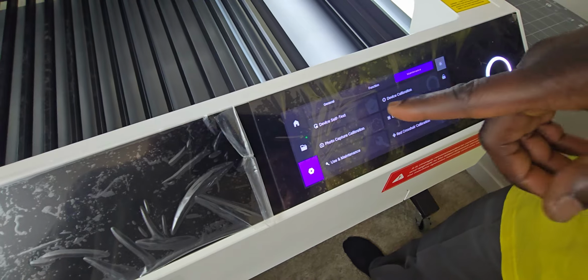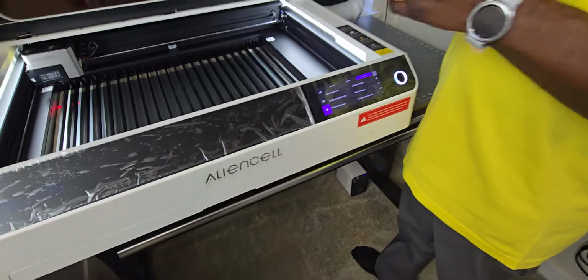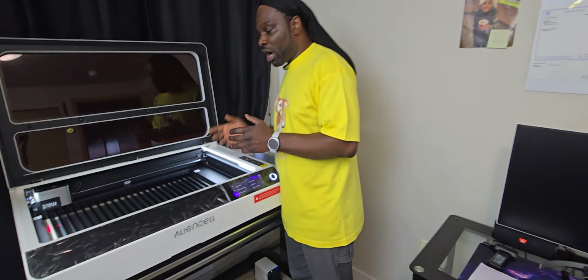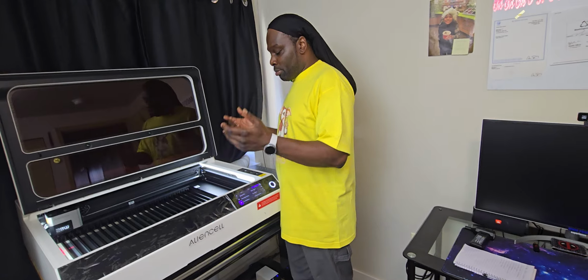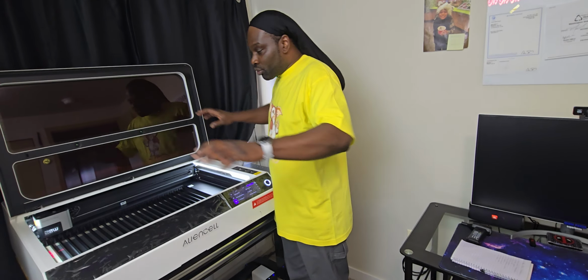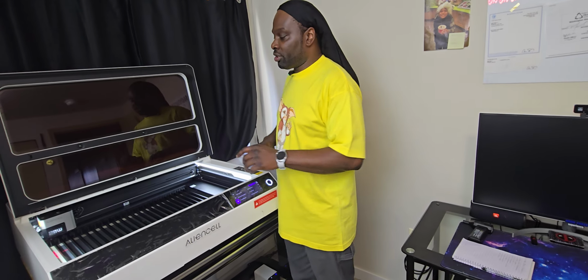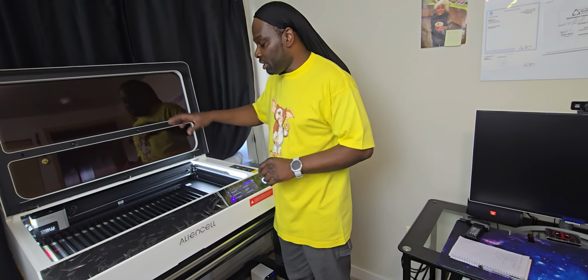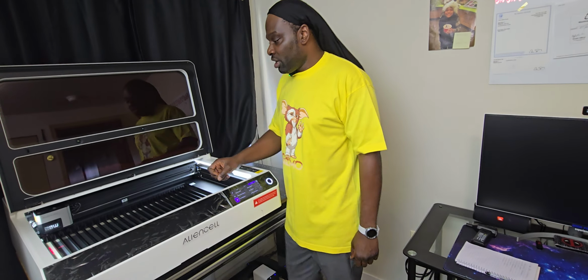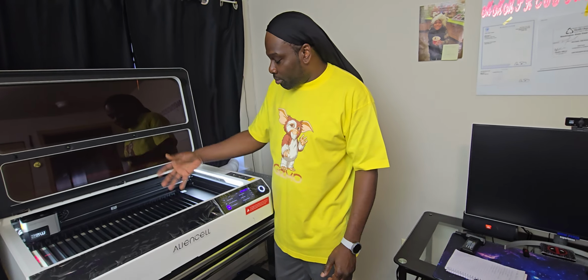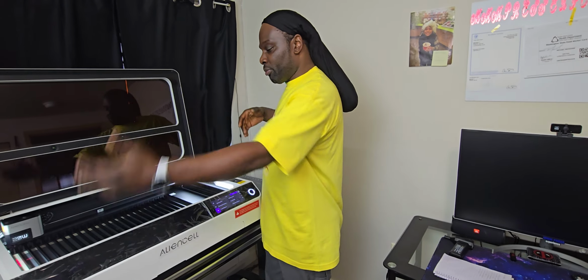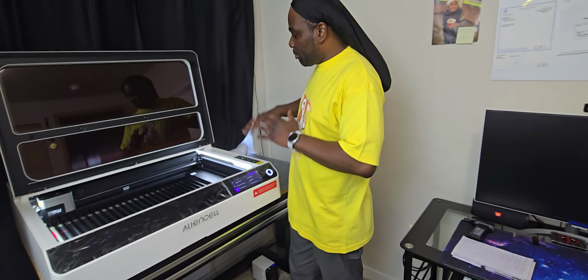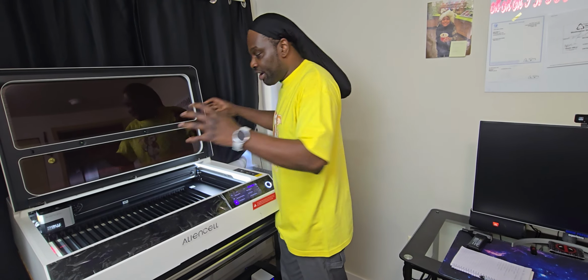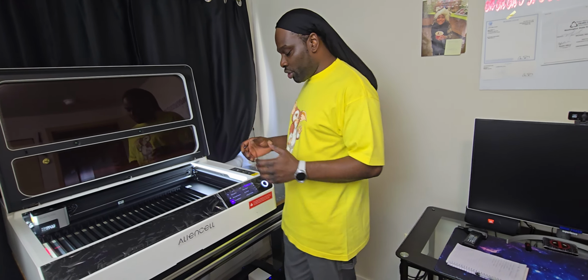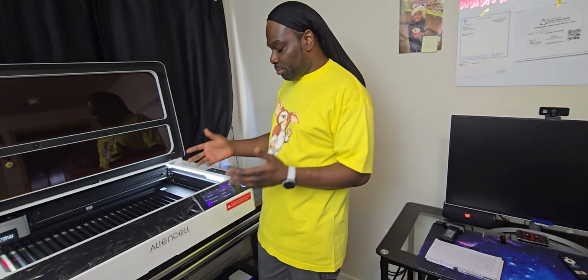Now let's go into maintenance. You have device self-test. What this is, if you think the machine has a problem or anything, maybe once in a blue moon, you might want to hit this button just to make sure everything works. It goes through and does a whole test of every component in here. It tests the cameras, tests your laser, tests to make sure the fan in the back is working, makes sure your screen in front is working, makes sure your lights are working. It just does a self test to make sure everything is working, and if there is an issue, it will let you know the machine has a problem.